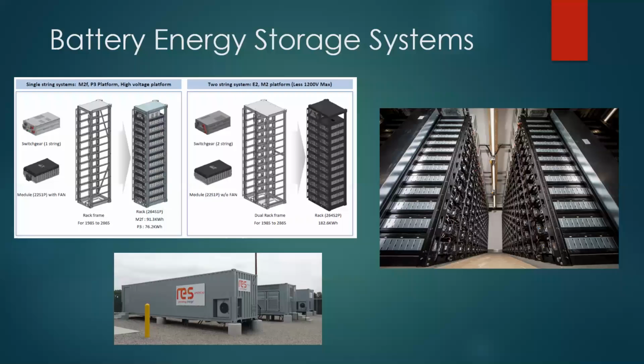So there are UL certifications that have come out recently that really drive the way that needs to be designed. Battery cell manufacturers have to run and pass stringent tests that measure the potential cell-to-cell thermal propagation within a module in order to be considered safe.